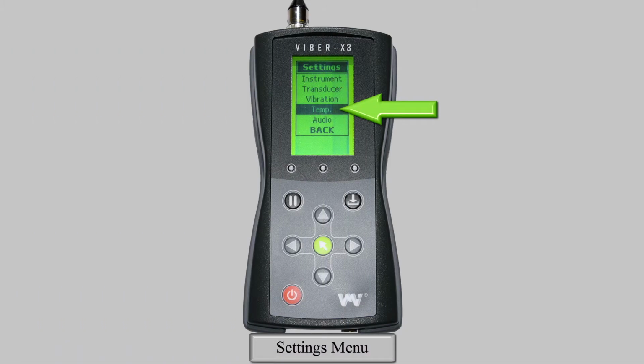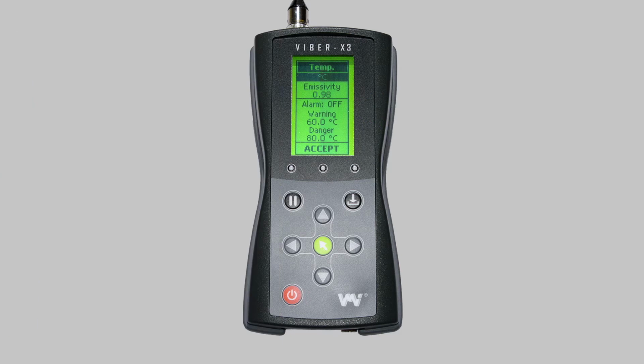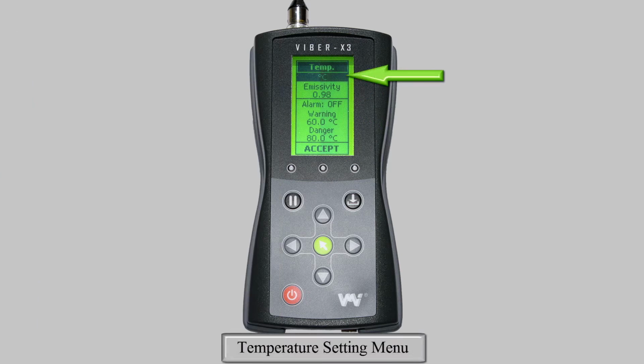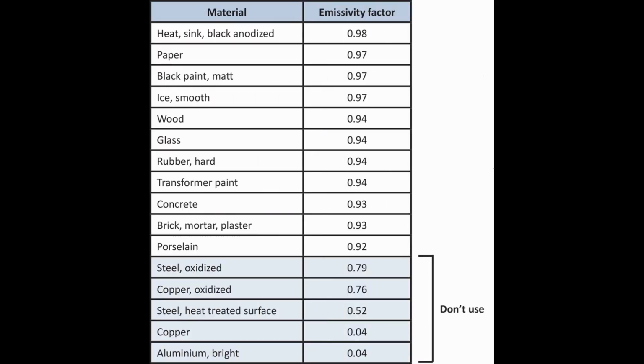Next we have the Temperature submenu. This is where you can select your unit to measure temperature in, change your emissivity factor, and set up your alarm levels. The options in this menu are changed the same way as for the vibration measurement settings. Highlight the option with the up and down arrow keys, then press either the left or right key to change the setting. When changing the emissivity factor, consult this graph, which is also provided in your instruction manual. An incorrect setting can lead to considerable errors when measuring temperatures.